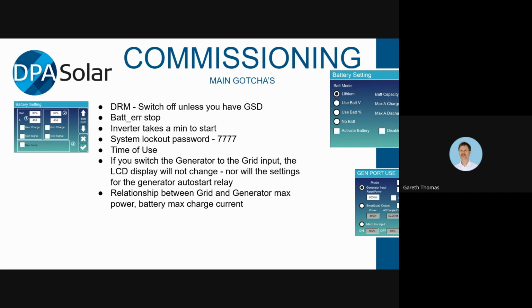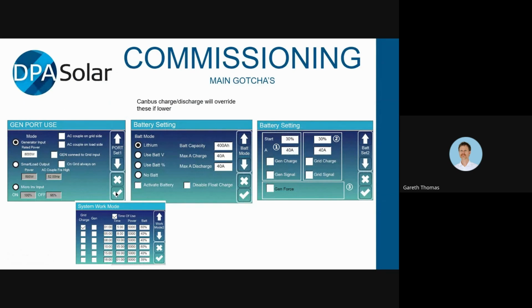And then the relationship between the grid and generator max power and battery max charge current. So all of these values are going to influence each other, and this is especially true for an off-grid type application. The comment from Derek as well, that all of these settings can be changed via the portal once you've connected it. So you can change every single setting remotely, which is a huge help. If you have a customer who's a long drive away and you don't want to go to site and you need to change something, you can just do it all from the portal.